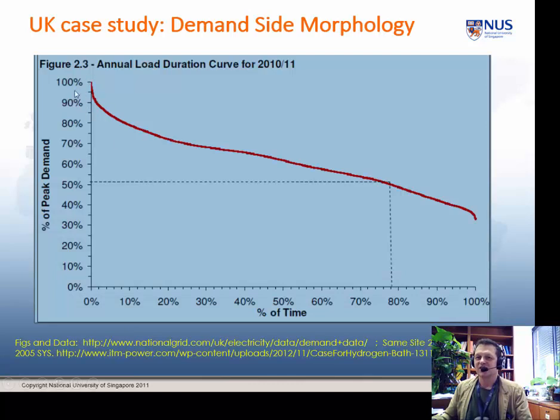This is an important graph. It's the percentage of peak demand for the percentage of time. So let's take peak, the absolute top. The lowest amount of time, in this case a few percent, you have to be at 90% network capacity, the better. Now, currently in the UK grid, 80% of the time, you're at about 50% of the grid capacity of peak demand. So that's a very useful curve to remember. It shows you how hard you're pushing the system, how much risk you're taking.